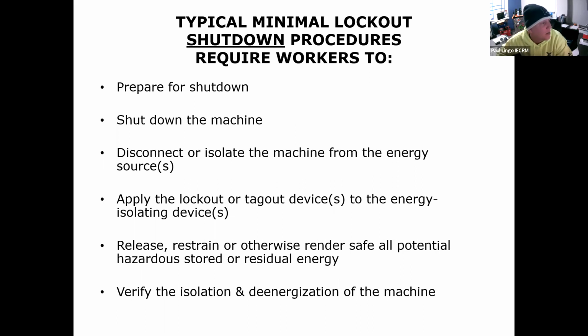Minimal steps: communicate, prepare for a shutdown, shut down the machine or energy, disconnect or isolate it, apply the tag, and render it safe, which means testing. Don't just lock it and tag it out and go back to work.